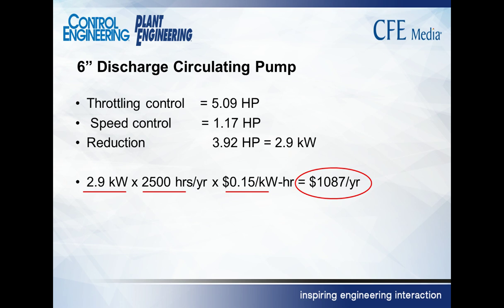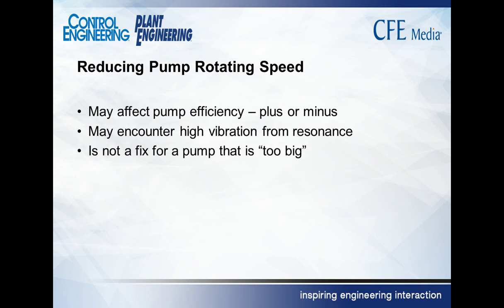And we're paying 15 cents a kilowatt hour for energy. Just do a little simple multiplication. You've saved yourself $1,000. You've got about a 10 horsepower motor on this to handle anything that it could possibly run across. Put a bigger motor on it. So you've got a 10 horsepower variable speed drive. Can you buy a 10 horsepower variable speed drive for $1,000? Maybe. About the right price. One year payback? That doesn't sound too bad.